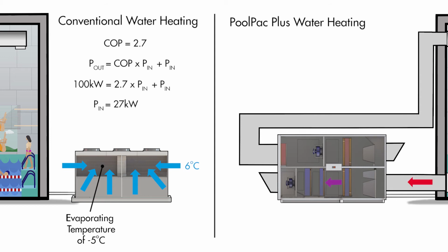In comparison, the DX heat pump for the PoolPac Plus will be absorbing heat from the energy-rich exhaust air after the heat recovery system. In this case, we would expect an air-on evaporator temperature of around 13.5 degrees and be at or close to saturation with a total enthalpy of approximately 40 kilojoules per kilogram. Compare this to the outside air, which is 6 degrees Celsius and has a total enthalpy of around 18 to 20 kilojoules per kilogram. Even after the heat recovery, the exhaust air is twice as energy-rich as the outside air.